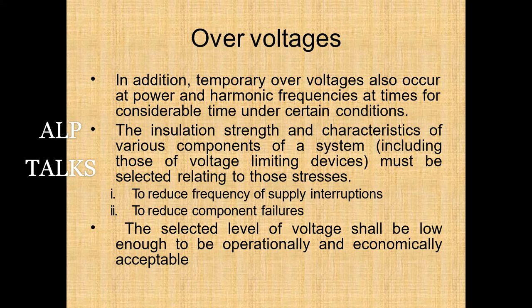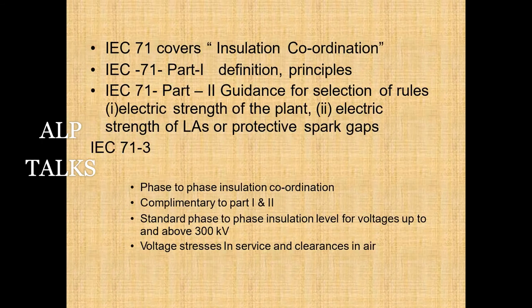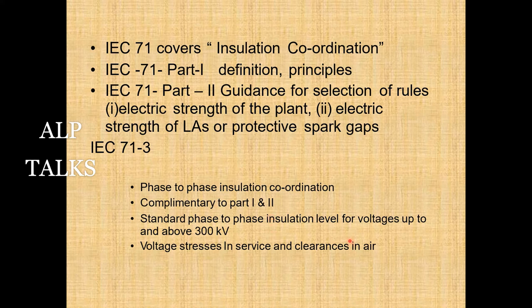The insulation strength and characteristics of all system components, including voltage-limiting devices, must be selected in relation to those stresses to reduce supply interruption frequency and component failures. The selected voltage level shall be low enough to be economically acceptable. IEC 71 covers insulation coordination: Part 1 gives definitions and principles; Part 2 gives guidance on selection rules and electric strength of protective spark gaps; Part 3 covers phase-to-phase insulation coordination, standard phase-to-phase insulation levels for voltages up to and above 300 kV, voltage stresses in service, and clearances in air.